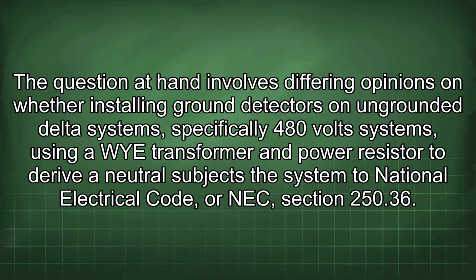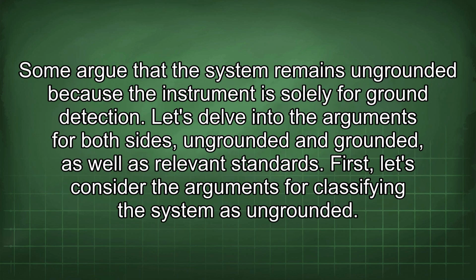The question at hand involves differing opinions on whether installing ground detectors on ungrounded delta systems, specifically 480-volt systems, using a wye transformer and power resistor to derive a neutral subjects the system to National Electrical Code, or NEC, section 250.36. Some argue that the system remains ungrounded because the instrument is solely for ground detection. Let's delve into the arguments for both sides, ungrounded and grounded, as well as relevant standards.